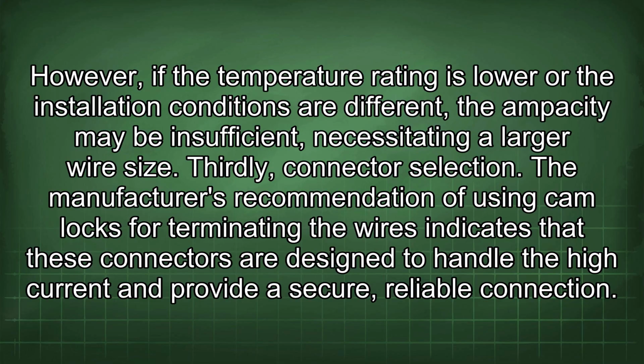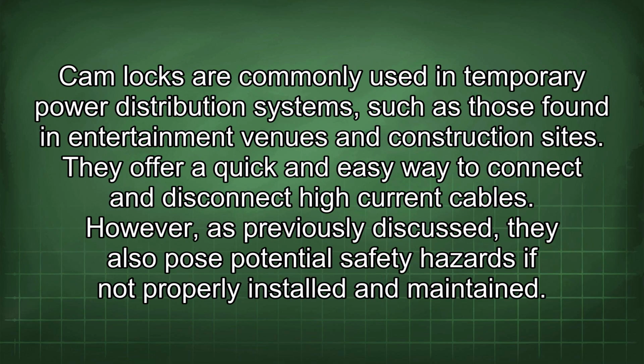Thirdly, connector selection. The manufacturer's recommendation of using cam locks for terminating the wires indicates that these connectors are designed to handle the high current and provide a secure, reliable connection. Cam locks are commonly used in temporary power distribution systems, such as those found in entertainment venues and construction sites. They offer a quick and easy way to connect and disconnect high current cables.